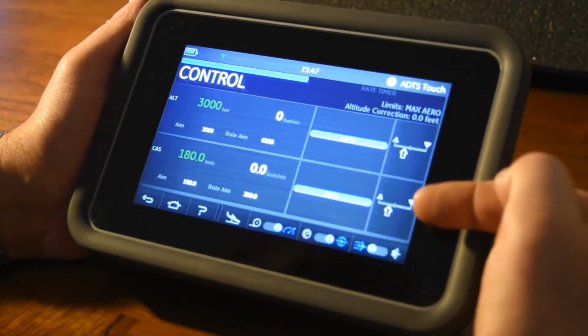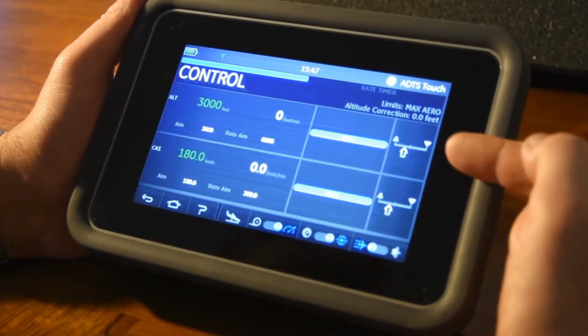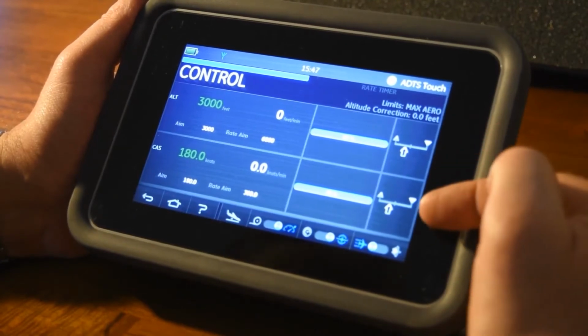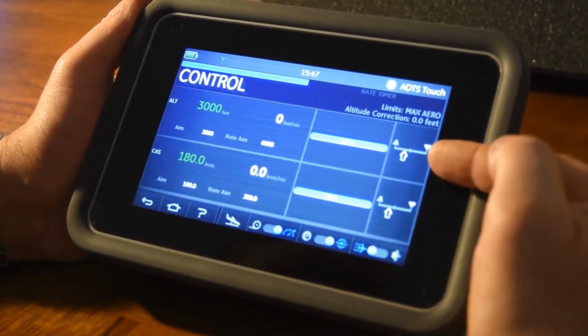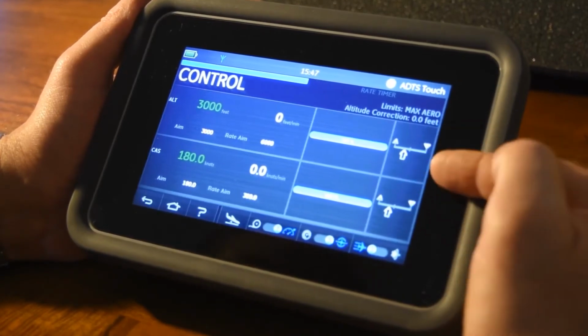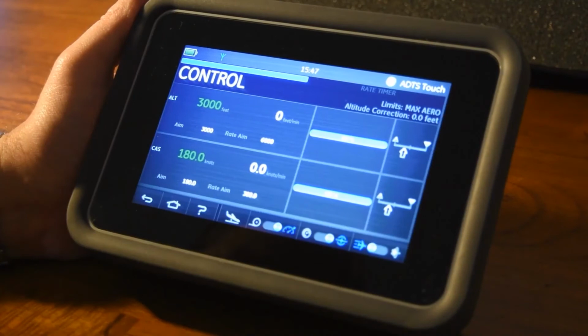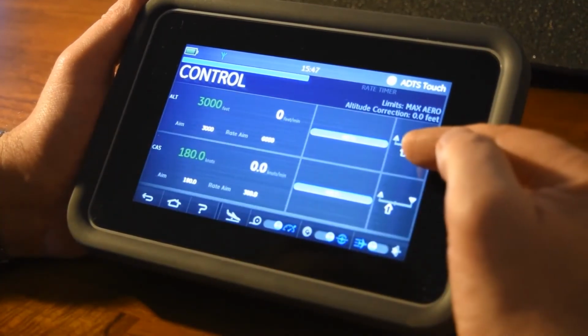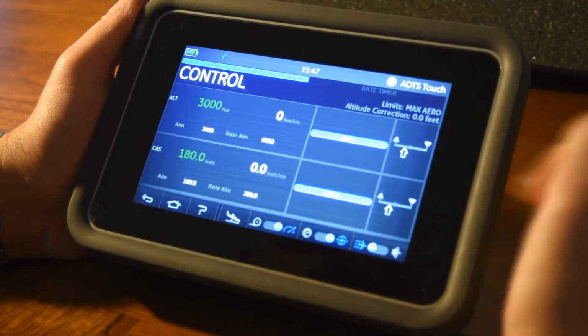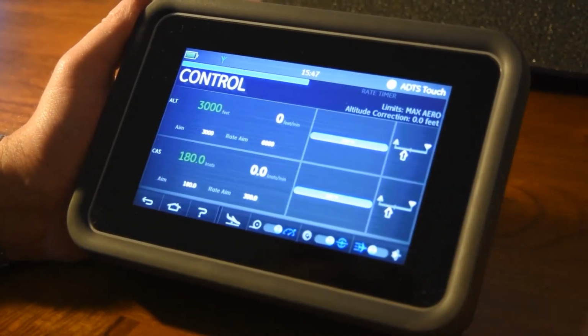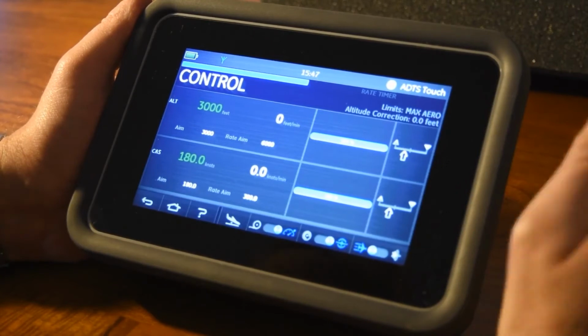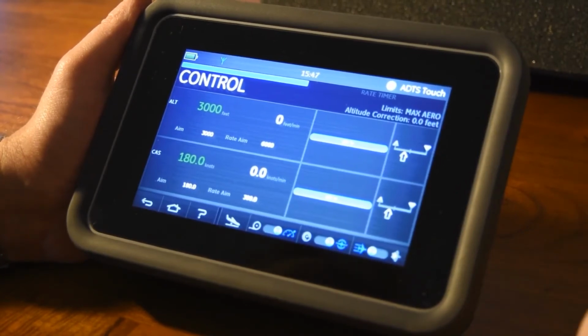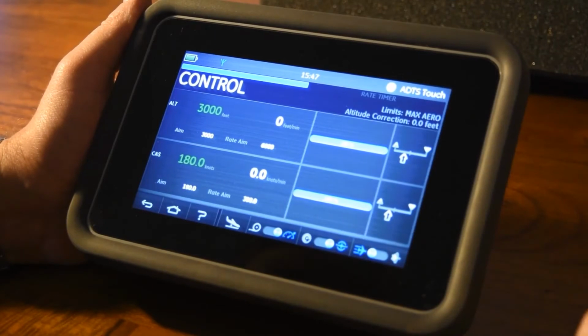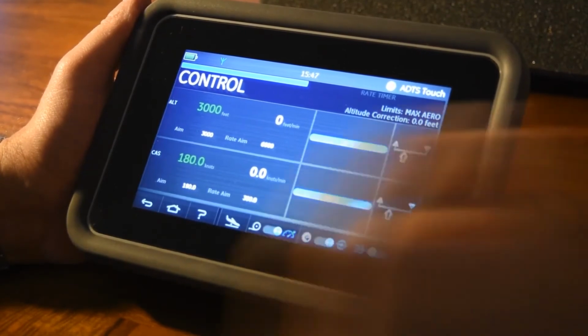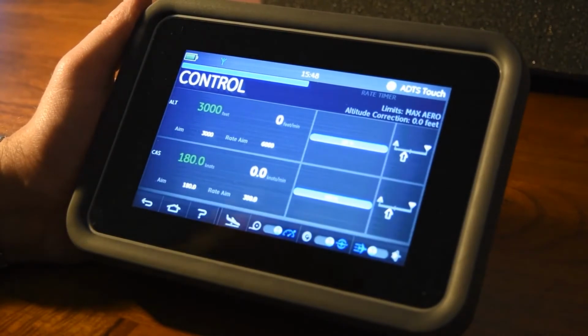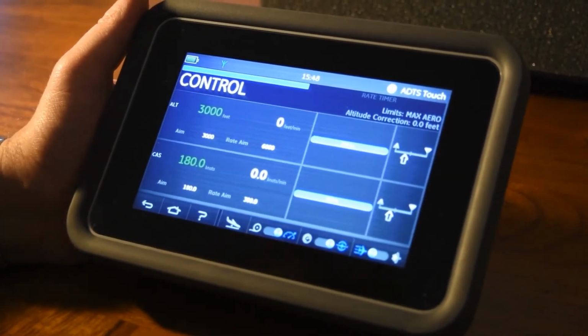Now this is a great feature on the right hand side of the screen. This is what I call the effort meter. This is telling us how hard those pumps are having to work in order to maintain the values that we've set. Ideally those two arrows should be right in the center there with this little point. So what this is telling me straight away, before I even go in to do a leak test, is I've got a leak, but the controllers are quite powerful, so they're able to control that leak and still maintain those set points. So for argument's sake, let's just see how bad that leak is.